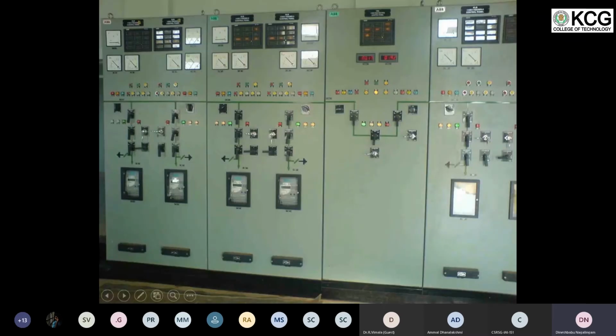What is a control panel? A panel which is used to control is called the control panel. So what do we control? We control the equipments in the switchyard, like isolators, breakers, earth switch. So you can see here from this control panel the list of equipments available. There is a mimic. A mimic is a representation of a part of the single line diagram. This is a mimic, the green color one. Some switches are there. These are called TNC switches, trip and close. It is used to operate the isolator and breaker. You have some LED indications. This is to show us whether the switch is in open position or closed position.